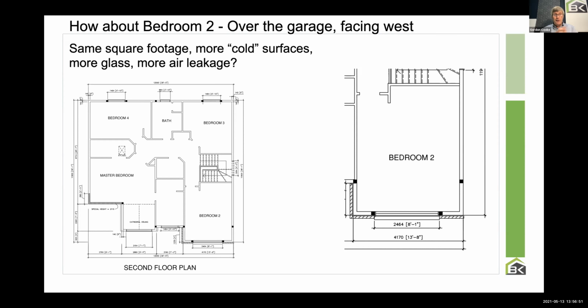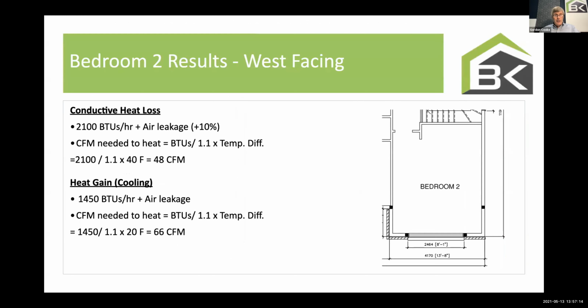It's the same 10 by 15 room, but it's got more cold surfaces, more glass, and potentially more air leakage, right? Room over the garage, a neutral pressure plane. Gee, I wonder if air's leaking into this room. And in fact, of course it may be. Air simultaneously may be leaking out of bedroom 3, but leaking into bedroom 2 because of stack effect, because you have a cold garage underneath it. So that's an interesting one.